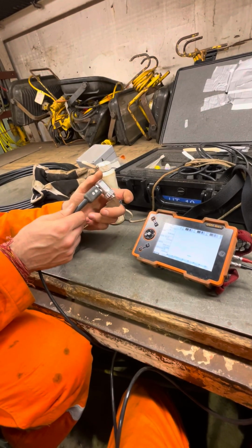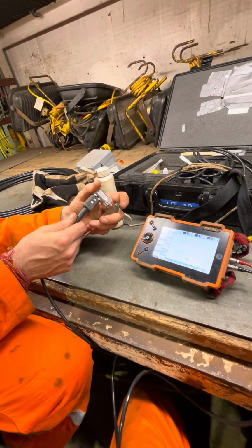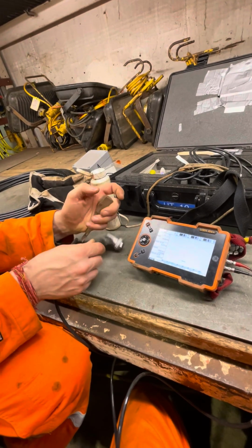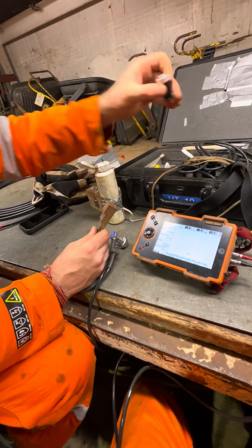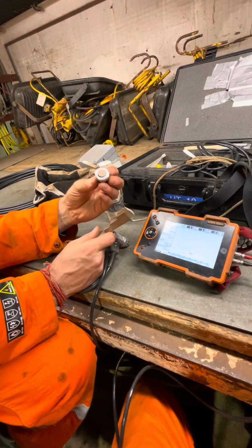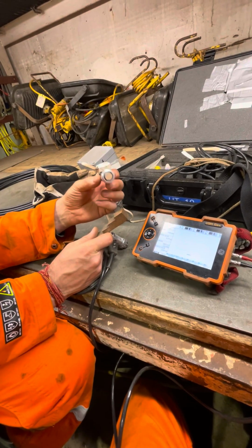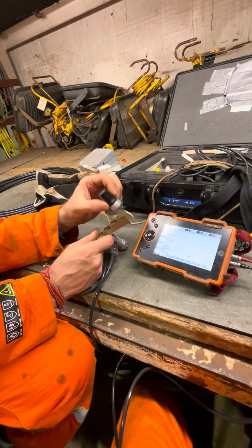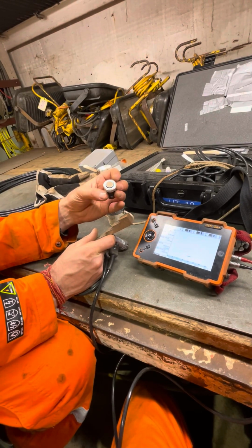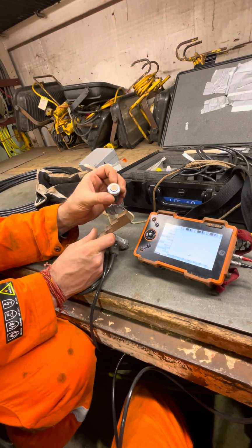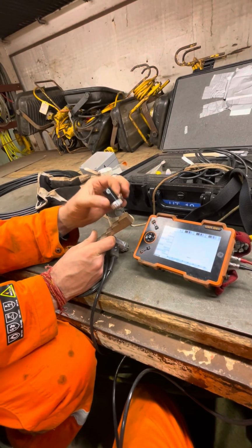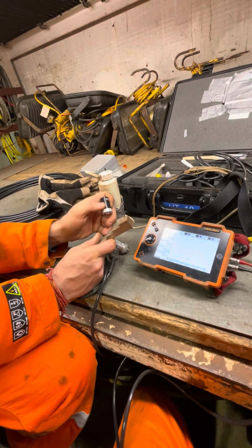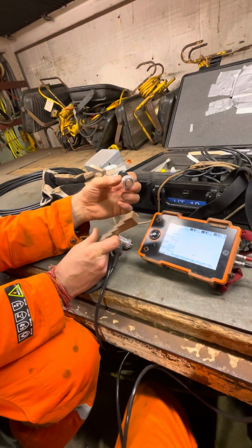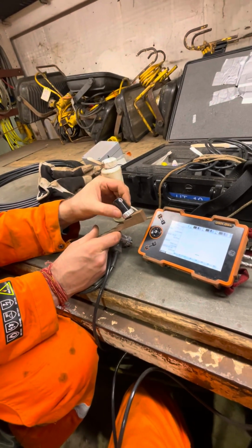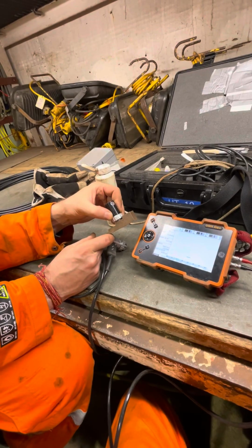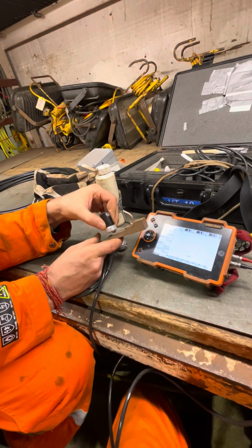Measuring with paint is considered incorrect, but we do it because it's easier. With paint, you should use the single probe to measure. That's the most correct option. That's why they send it. But for now, we won't be doing that because the signal is much worse. And that's why we usually don't. But the most interesting thing here is that you can set it to a specific thickness, for example, to 15. And everywhere with paint, it will show the same value.